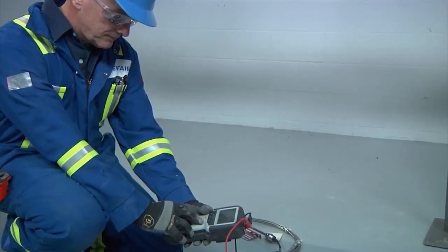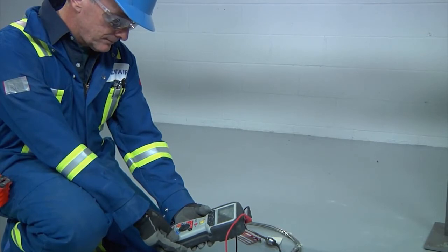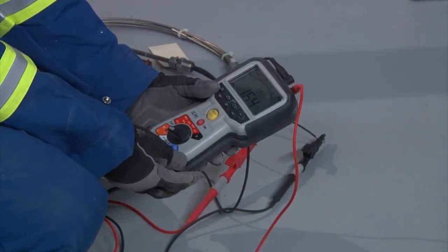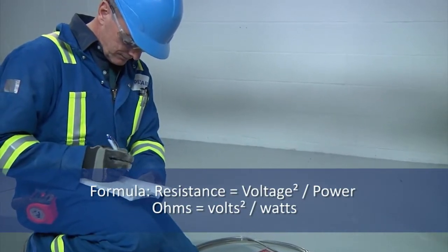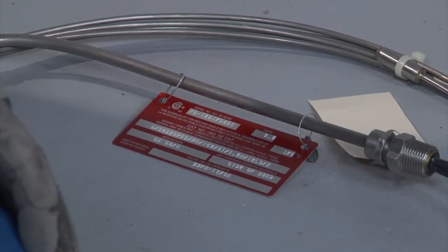Now measure the resistance of the heating cable. Most MI heating cable resistances are less than 100 ohms. The measured value should be approximately equal to the design value. The design value resistance can be calculated using the formula: resistance (ohms) = volts² ÷ watts. Voltage and wattage can be found on the heating cable identification tag.